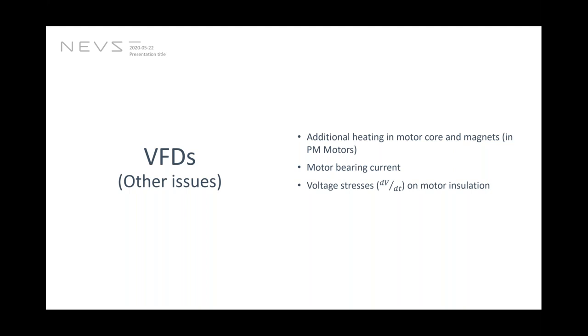Another thing is the voltage stress, the dv/dt in the motor insulation. It's very important because the insulation classification, whatever we have mentioned in the standard, will be for the temperature and dv/dt. So basically, the stress on the insulation is not only due to the voltage across the insulation, it's how fast it is rising. And that affects the life of the insulation quite a bit and might cause insulation failure as well.